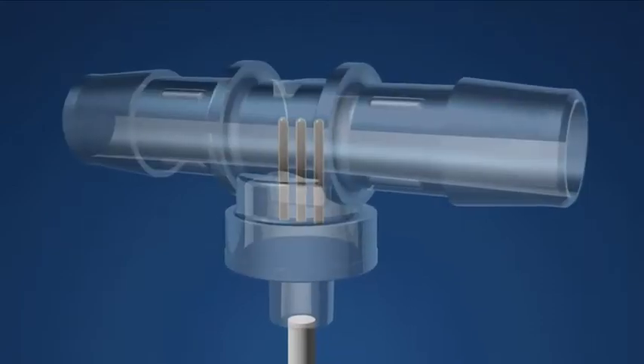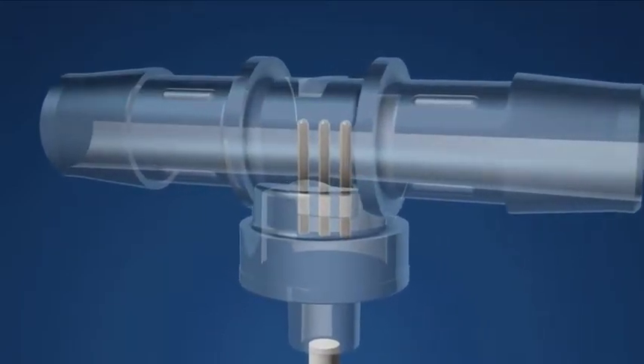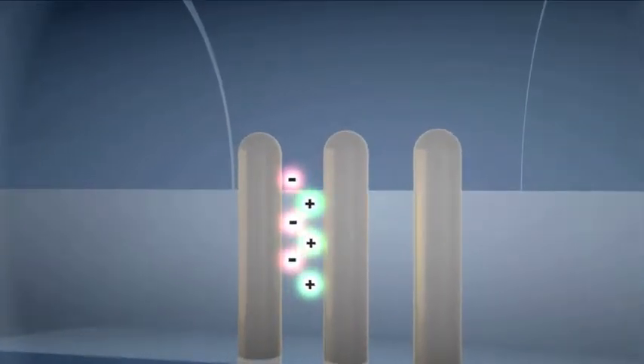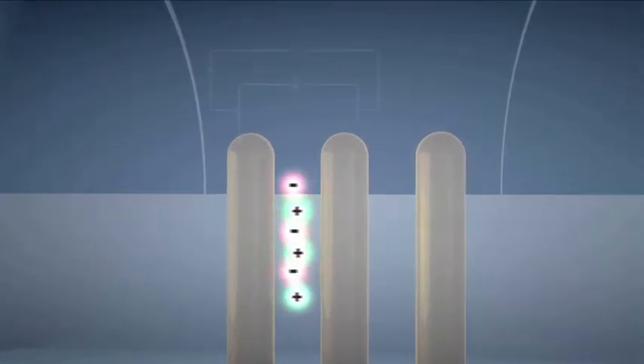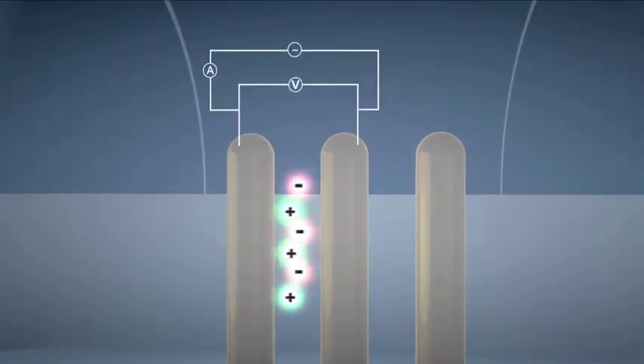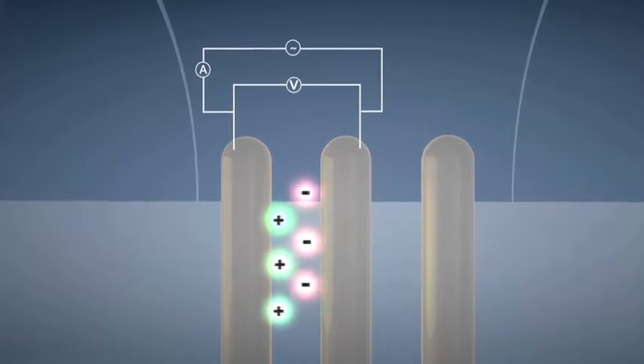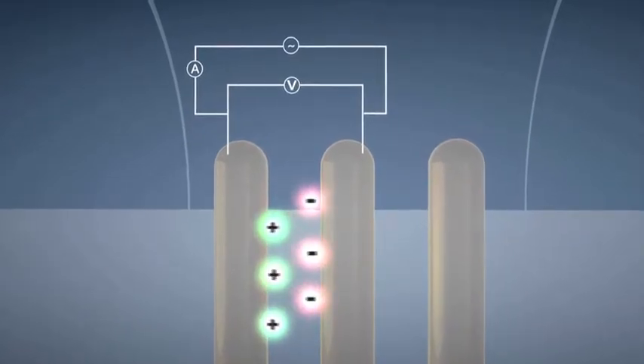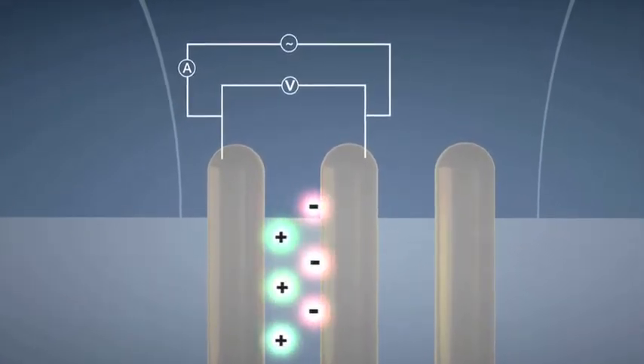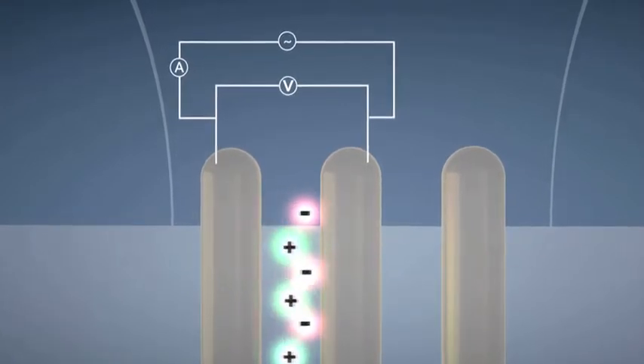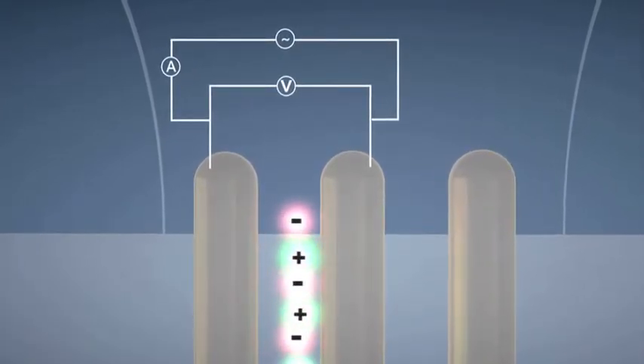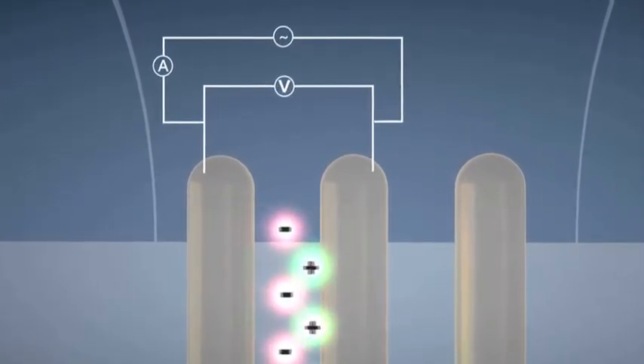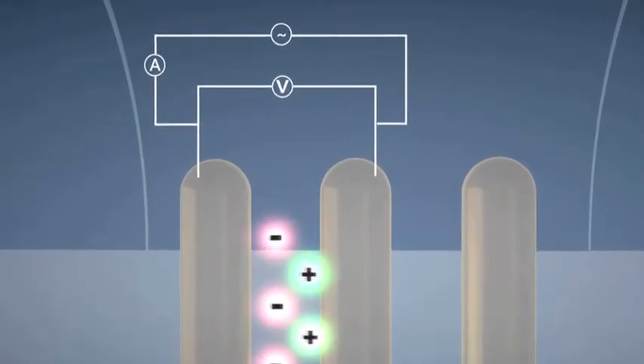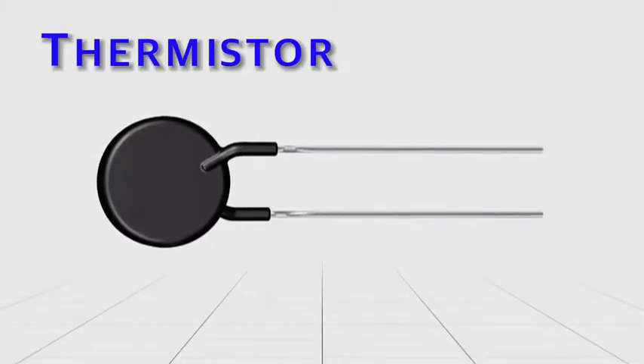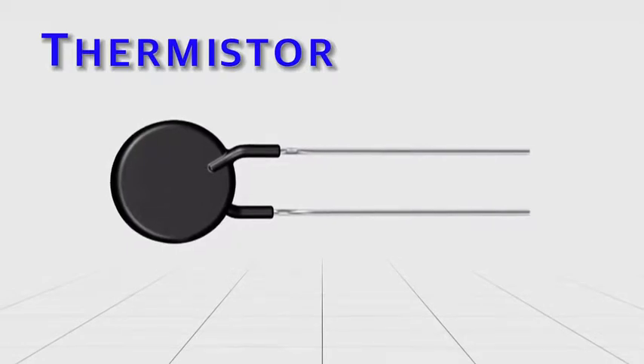The electrical conductivity of a solution is measured by determining the resistance of the solution between two electrodes separated by a fixed distance. An alternating current is used in order to avoid electrolysis. The resistance, which is the inverse of conductance, is measured by a conductivity meter. Ideally, the monitor offers automatic temperature correction. The temperature measurement within the sensor is an element called a thermistor.